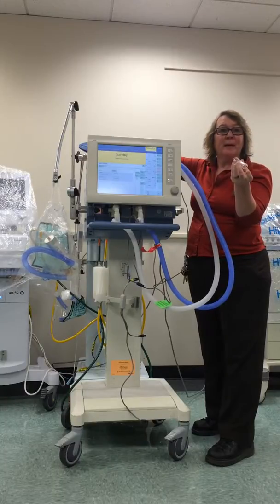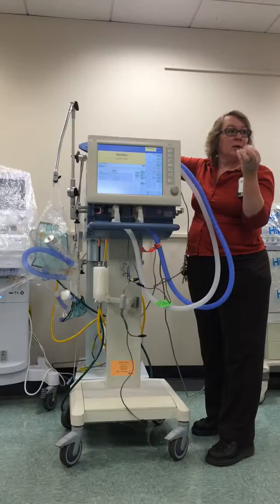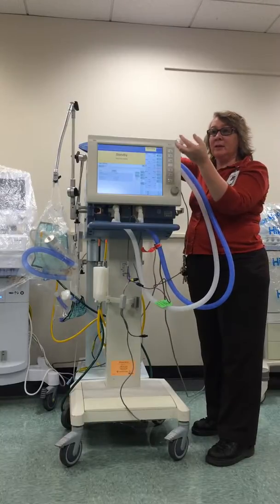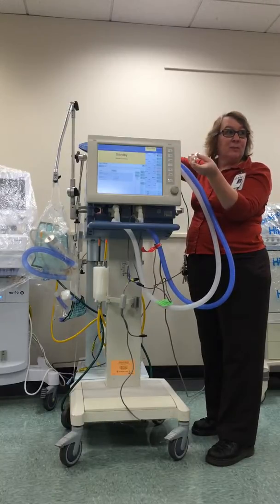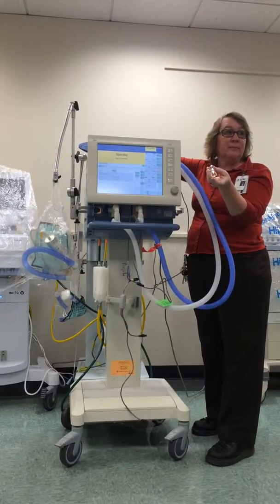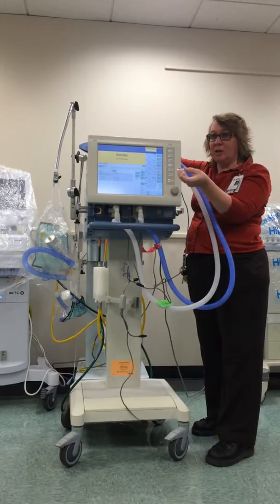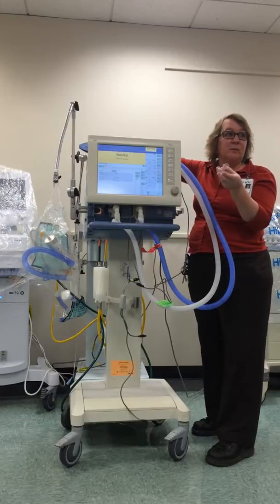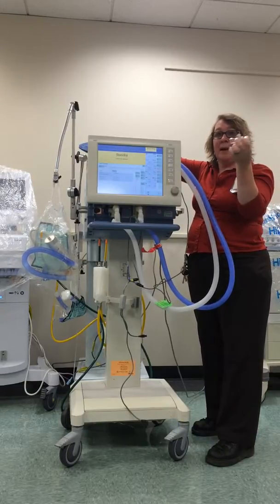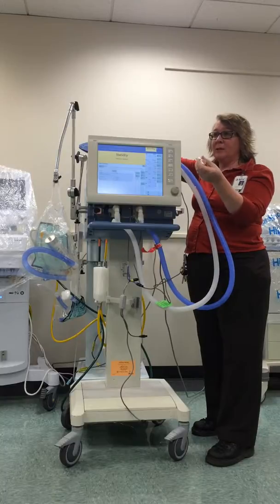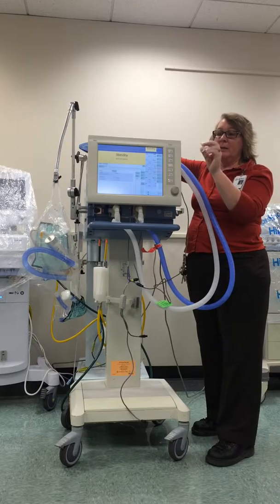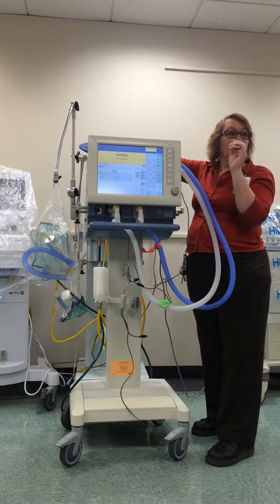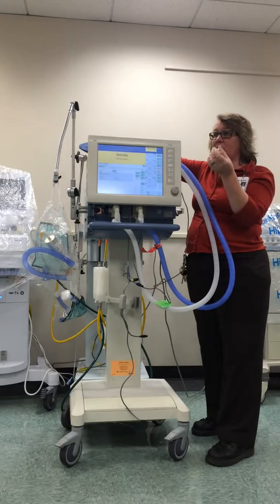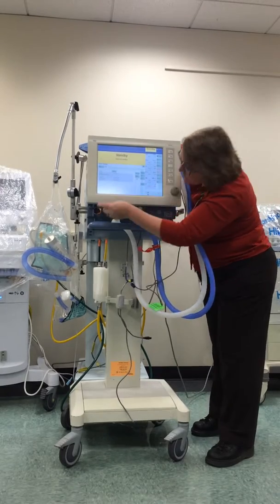So if this goes bad, your ventilator won't work. If you're running the ventilator and it tells you you need to calibrate the flow sensor, and you calibrate the flow sensor and it won't pass, you need a new one. And that means you need to bring this to me and let me double check first, and then I can go get one from Mr. Vosper. But clinically, these go bad too. So if it says to calibrate the flow sensor and you can't get it to calibrate and pass calibration, then you have to get a new one of these. It will not read any numbers without a correct flow sensor, because that's how it's measuring the flow and all the numbers that are going to the patient.